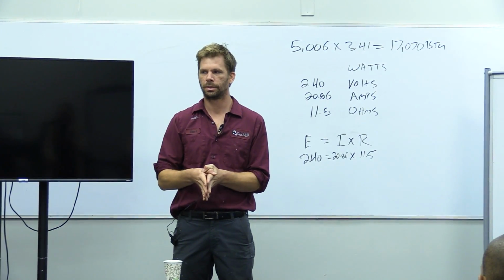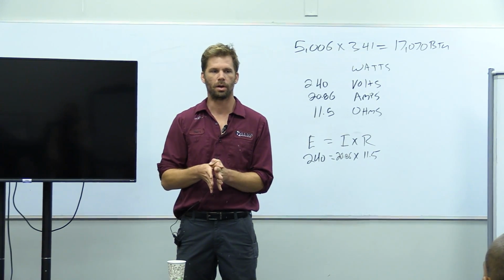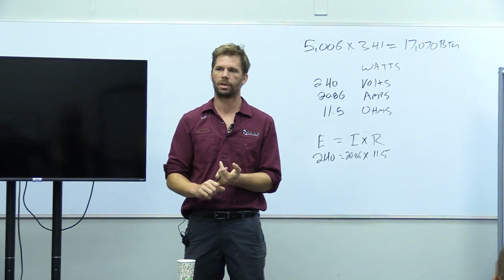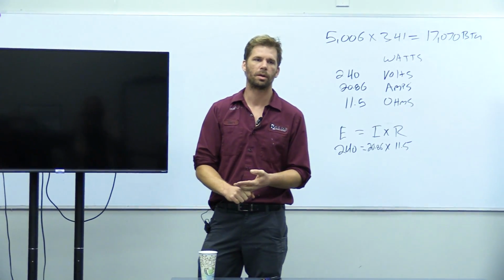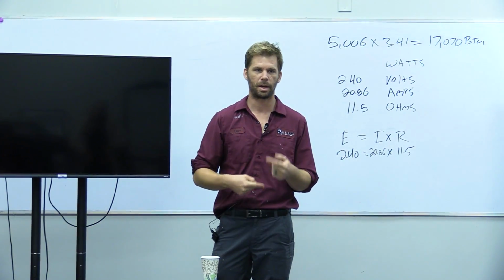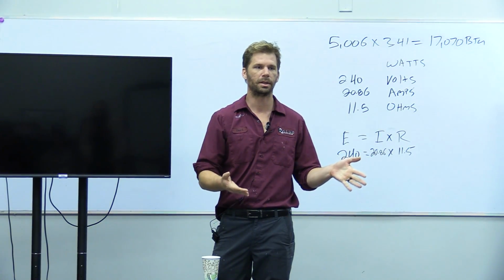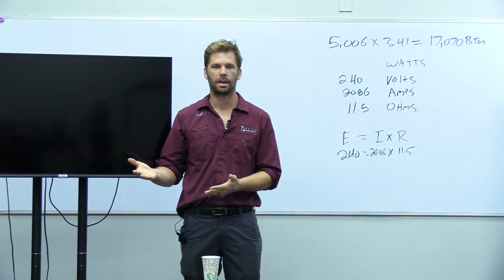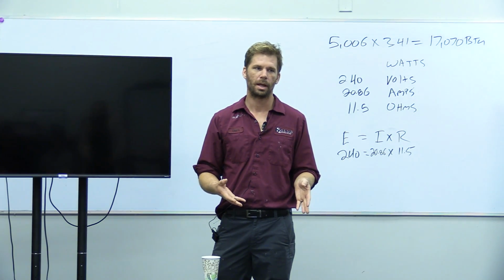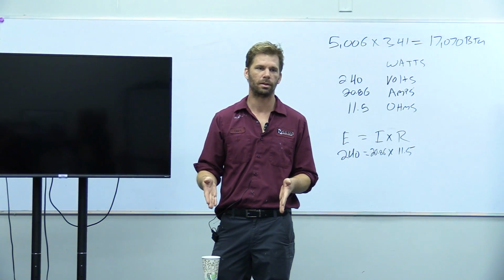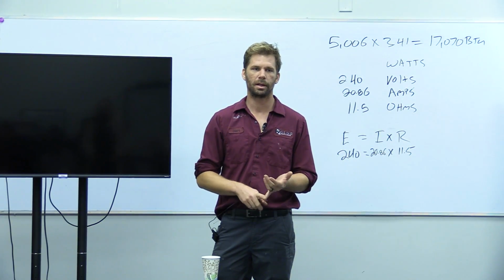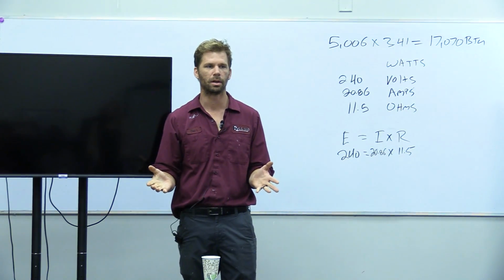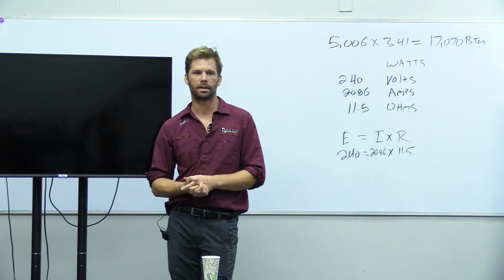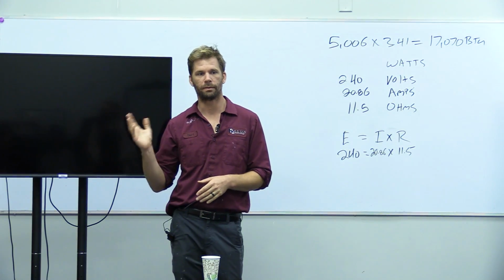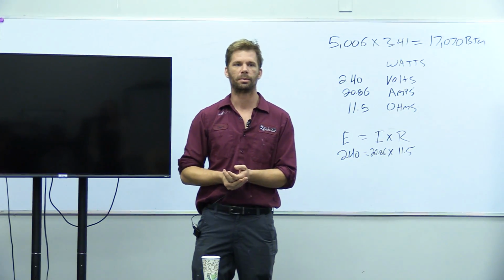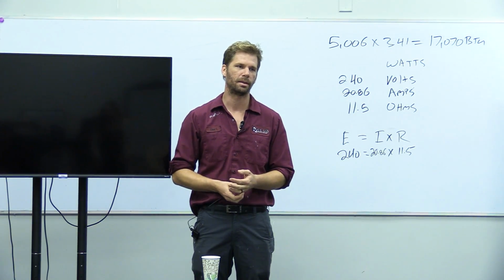Anytime a heat exchanger is cracked, you need to think about this happened for a reason. Something's wrong here. Something's wrong with my water flow. Something's wrong with my safeties, not turning off my heater. Maybe my water pressure switch has failed, so my heater keeps trying to run at night after the pump shuts off. I'm gonna quote a heat exchanger, but I'm gonna put in the notes, and I'm gonna have the conversation with the customer that after we put this new element in, we can test this, and likely there's something that caused this failure that we're gonna run into that we need to diagnose. So you've prepared the customer, and also the returning technician doesn't just replace a part and not pay attention to what might have caused that. Like testing when they shut off the pump, does the heater actually shut off? Replace the part, leave the customer with the same problem, eventually the new part's gonna have the same issue.